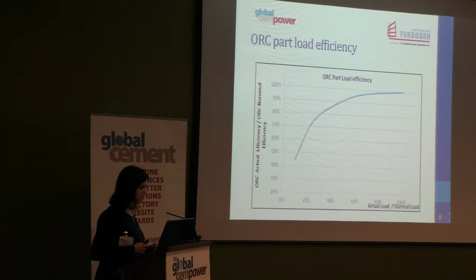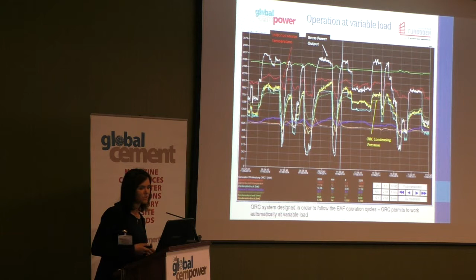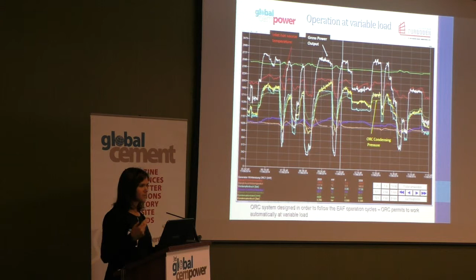This is an example of a working unit connected to a batch process. Every hour and a half, the thermal power available for the ORC decreases. The white line indicates the gross power output of the unit, and the red line is the hot source temperature. Here 2.7 megawatts is produced during this time. When the temperature of the hot source decreases, the power input decreases, and consequently the power output decreases too. We end up working at around 300 kilowatts, about 10% of the load, and this happens automatically, so we don't need any external signal saying that something around the ORC is changing.